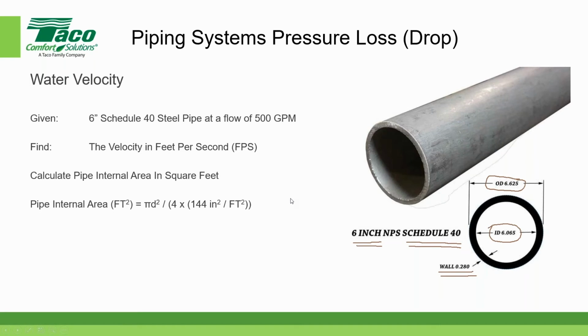The internal pipe area in square feet is equal to pi d squared divided by 4, divided by 144 to convert from square inches into square feet. If we simply plug in the numbers, the only numbers we have to plug in are pi and the diameter. If you use your calculator and plug in the values here, you'll come up with an internal area of 0.2006 square feet.